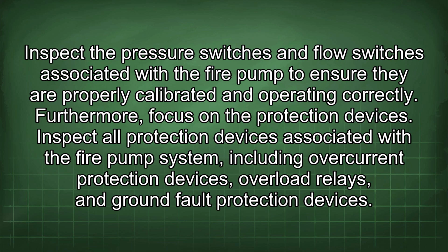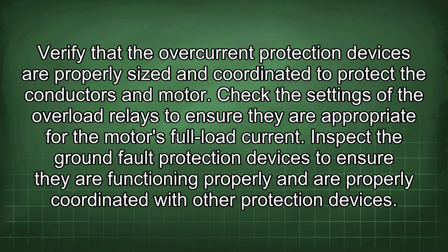Furthermore, focus on the protection devices. Inspect all protection devices associated with the fire pump system, including overcurrent protection devices, overload relays, and ground fault protection devices. Verify that the overcurrent protection devices are properly sized and coordinated to protect the conductors and motor. Check the settings of the overload relays to ensure they are appropriate for the motor's full load current. Inspect the ground fault protection devices to ensure they are functioning properly and are properly coordinated with other protection devices.